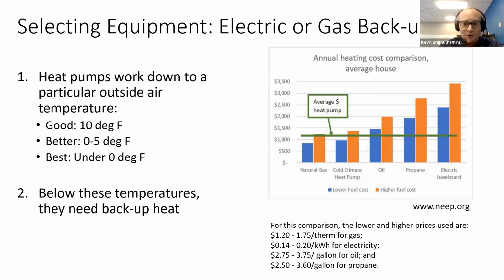In my house, for instance, the ductwork was already sized within the wall cavity and couldn't easily be increased in volume to account for stronger airflow. So I was interested in a best heat pump, one that worked down to minus 15 degrees. But I quickly found out that due to the limitation of my duct size, I'd be forcing a lot of air through a very narrow cavity, which would create noise issues within my home if we went with that model.